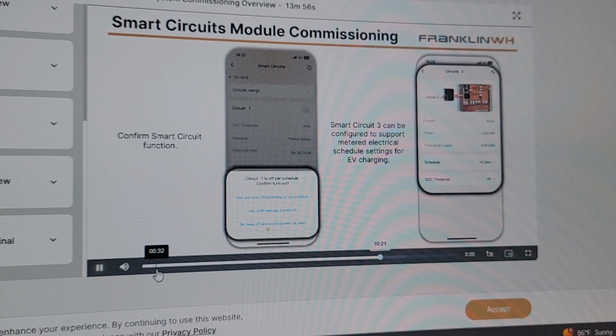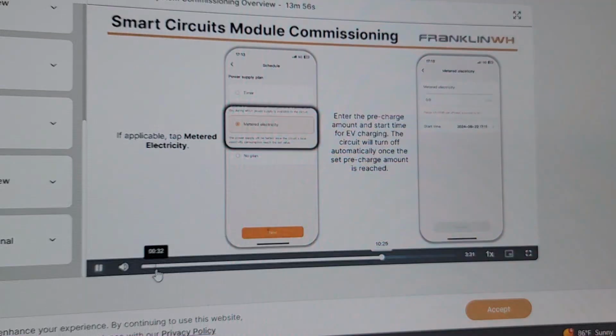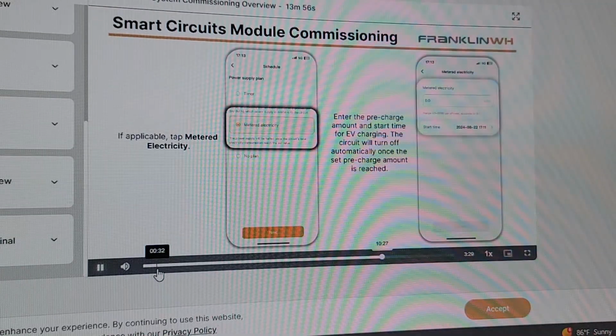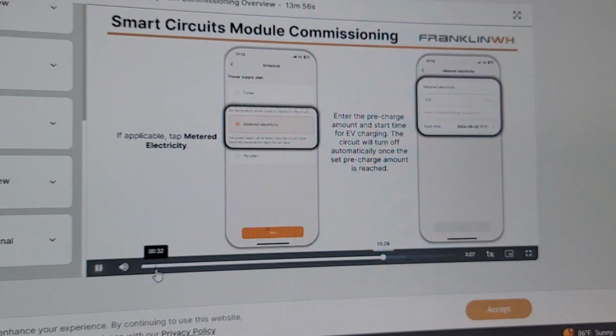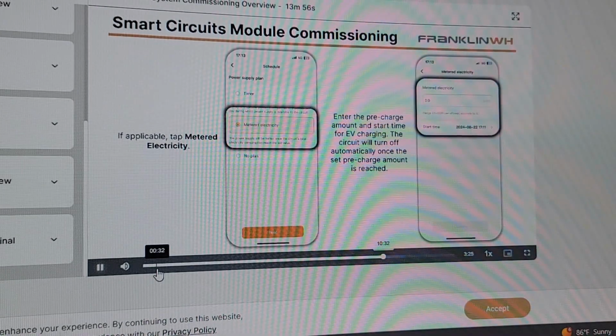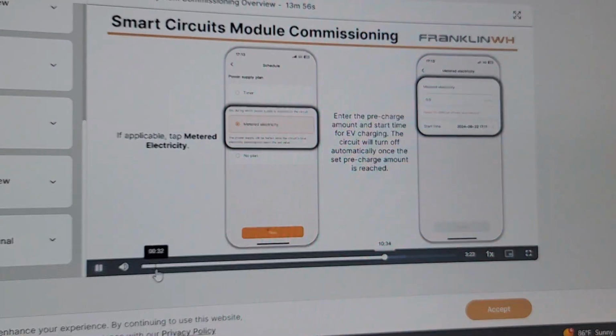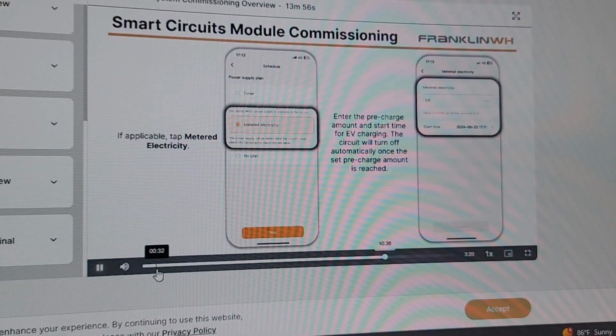Confirm Smart Circuit function. Smart Circuit 3 can be configured to support metered electrical schedule settings for EV charging. If applicable, tap Metered Electricity. Enter the pre-charge amount and start time for EV charging. The circuit will turn off automatically once the set pre-charge amount is reached.